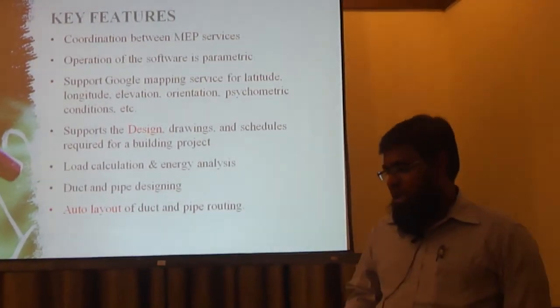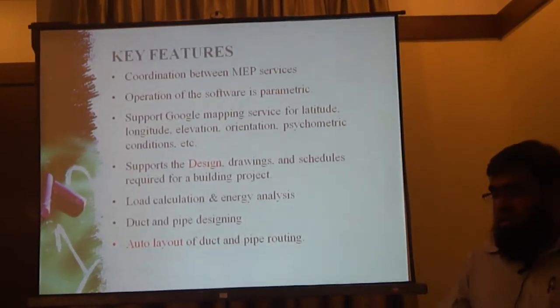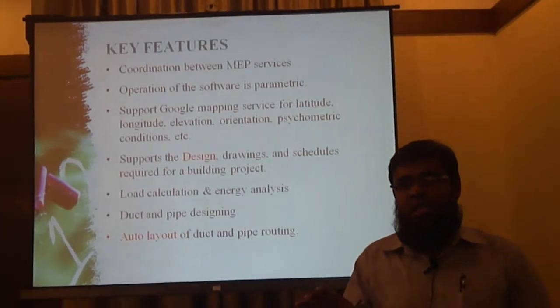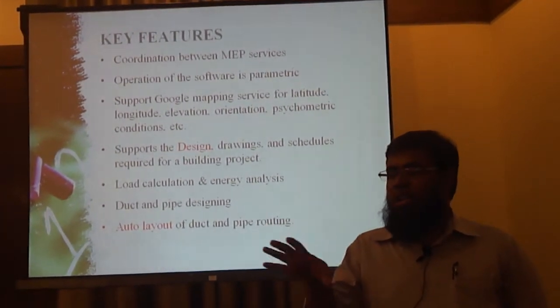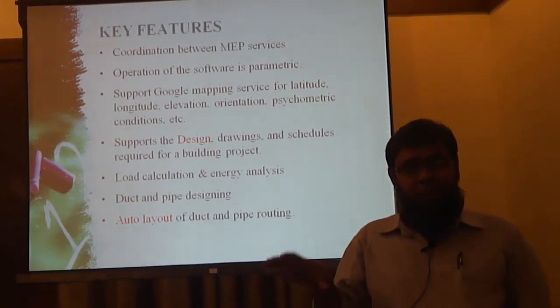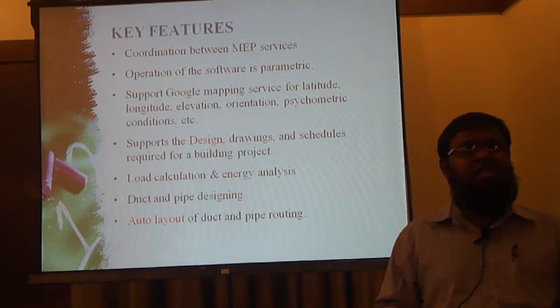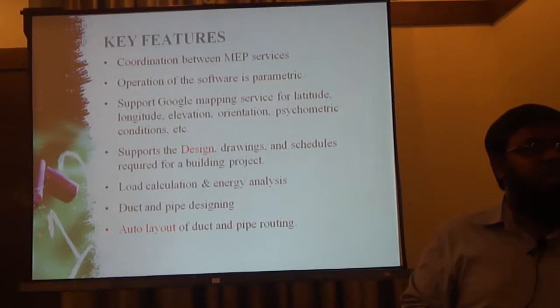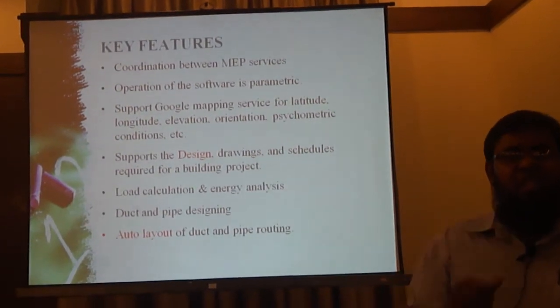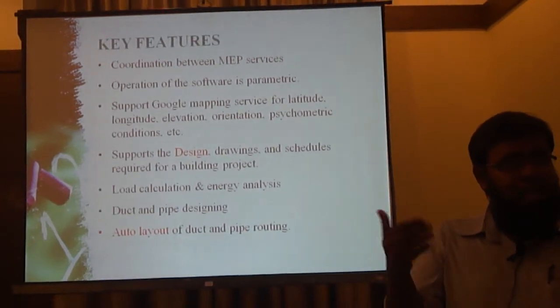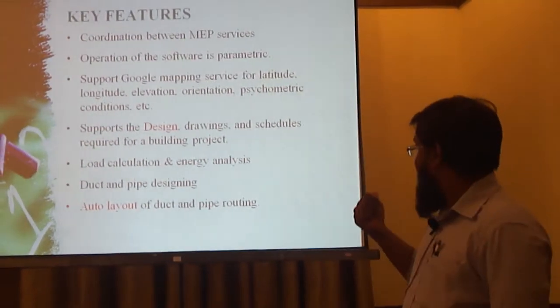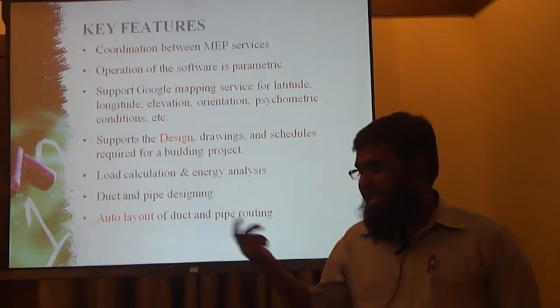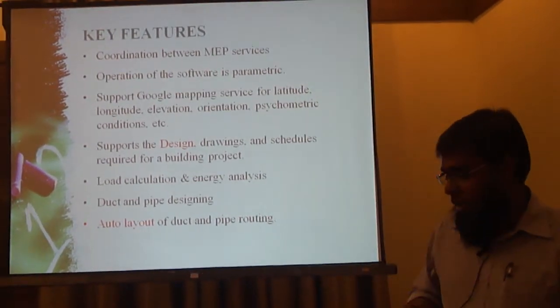The third point is very interesting — load calculation. It directly coordinates with Google Maps. Normally ASHRAE has given information for a particular city only, not for a particular location or building. For example, for Hyderabad the latitude is 17.45, but within Hyderabad different locations have different elevations, and because of that the psychrometric conditions, latitude and longitude will differ. With the Google Maps link, you can get exact location information, and this is available in Revit MEP.